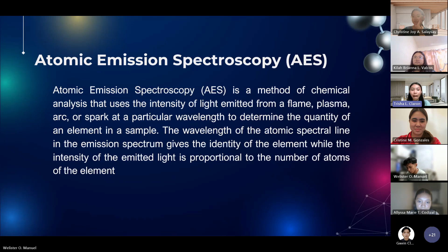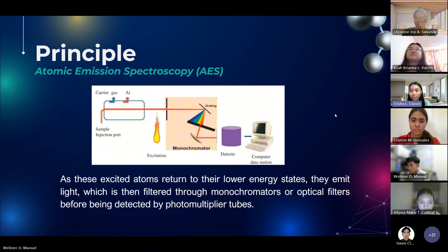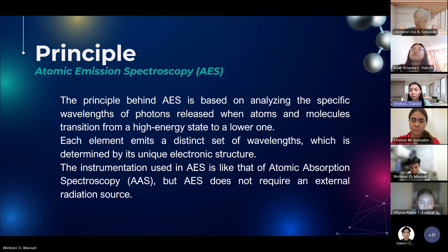And as stated earlier, monochromators separate our individual wavelengths through a single exit slit. And also, in terms of the excitation source for atomic emission spectroscopy, we use ICP-AES or ICP-OES, which is known as the inductively coupled plasma that can reach temperatures up to 10,000 Kelvin. And yes, as I've said earlier, it is used as an excitation source. So other plasma sources, next slide.